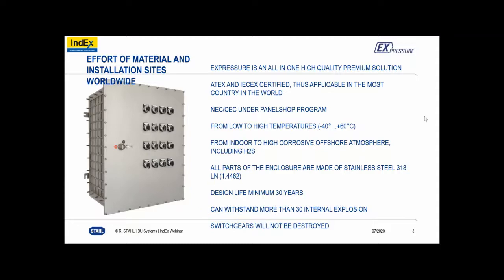What I also see is the last point: the switchgear will not be destroyed. Yeah, because we have a low overpressure inside of the enclosure, your switchgear will not be destroyed. That's also a point we have to mention at this stage, because it's so simple. Of course, you have to make an FAT again and check the components inside, whether they are manually and electrically still in good shape and the characteristic of the protection has not changed. But after an explosion, we can say you can switch on again.